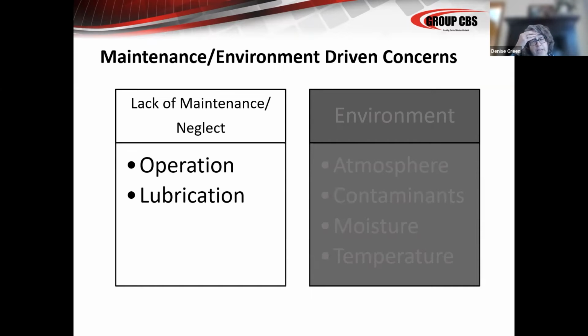So I briefly discussed this. So the maintenance and environmental concerns with circuit breakers: when you don't maintain a breaker, there is an operational disadvantage. When a breaker stays in a closed position for an extended period of time without being maintained or cycled, it is less likely to operate in the expected way. So my boss, Finley Ledbetter, likes to use the example that if you stood with your palms pressed together in front of you as hard as you could for 5 years, and then tried to open your hands as quickly as possible, it probably wouldn't happen like you expected it. So that is a situational breaker maintenance concern with lack of operation.